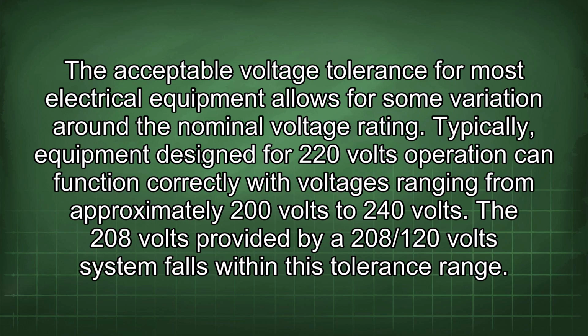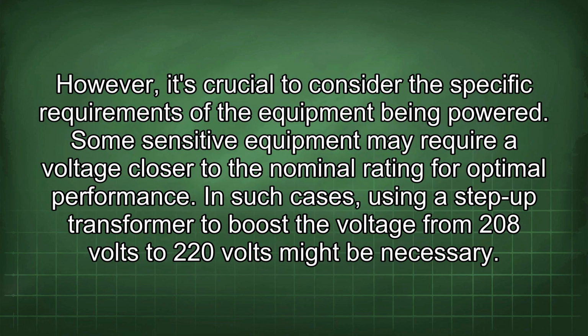The 208 volts provided by a 208/120 volt system falls within this tolerance range. However, it's crucial to consider the specific requirements of the equipment being powered. Some sensitive equipment may require a voltage closer to the nominal rating for optimal performance. In such cases, using a step-up transformer to boost the voltage from 208 volts to 220 volts might be necessary.